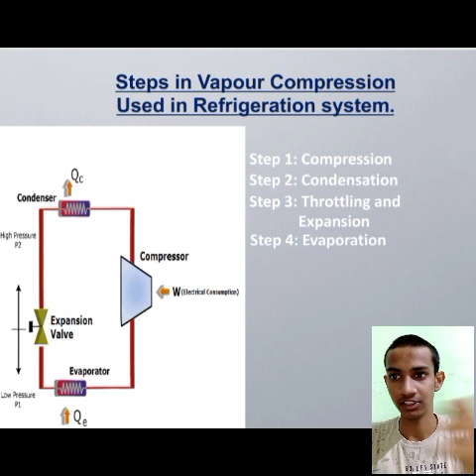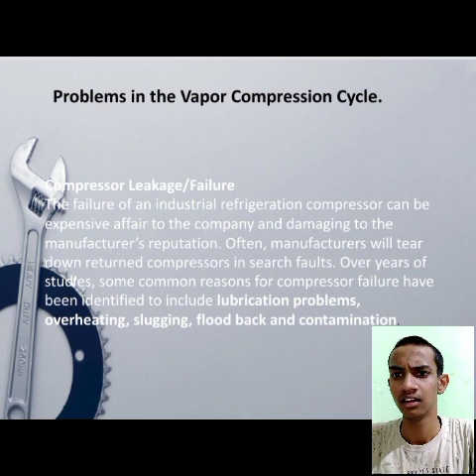Problems in the vapor compression cycle. Compressor failure. The failure of an industrial refrigeration compressor can be an expensive affair to the company and damaging to the manufacturer's reputation. Often, the manufacturer will tear down the returned compressor in search of clues. Over years of studies, some common reasons of compressor failure have been identified to include lubrication problems, overheating, slugging, flood back, and contamination.